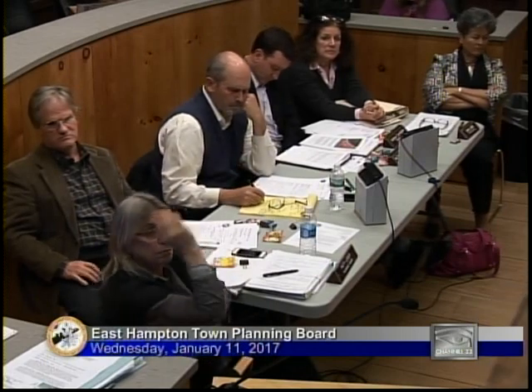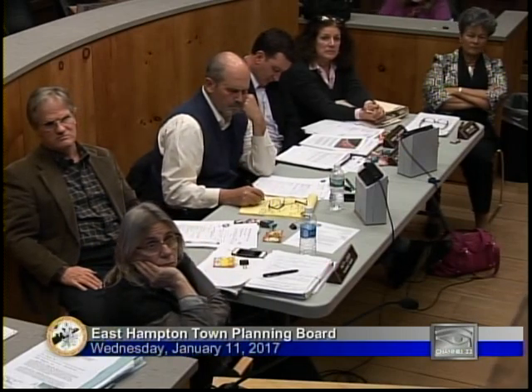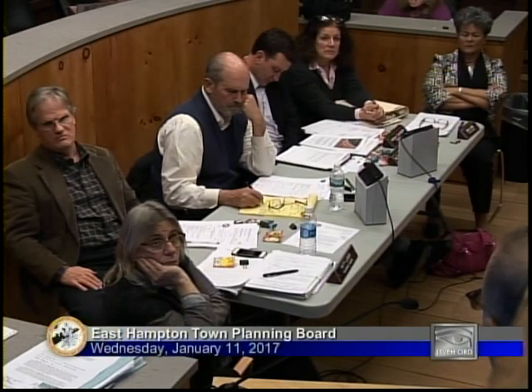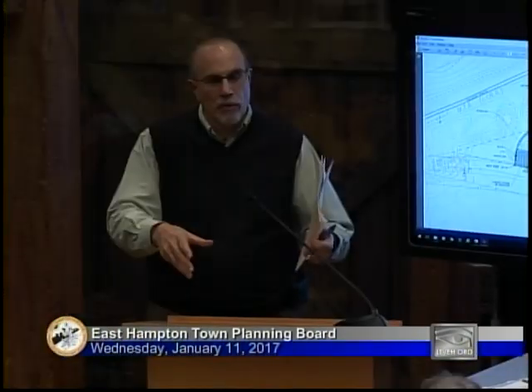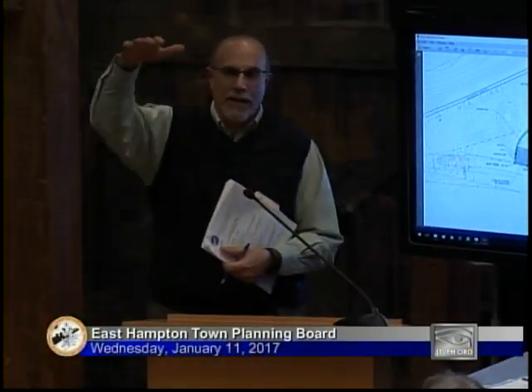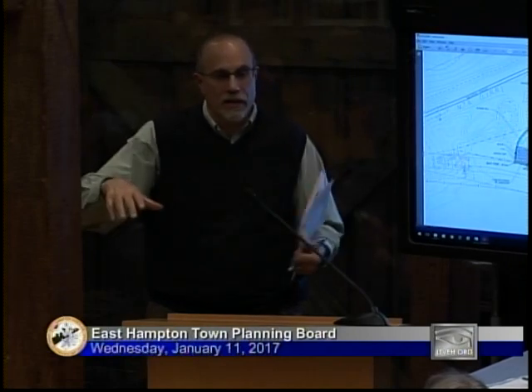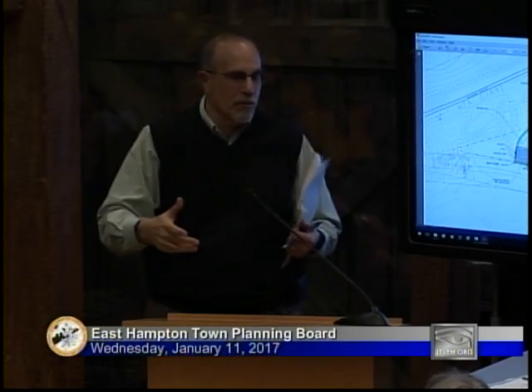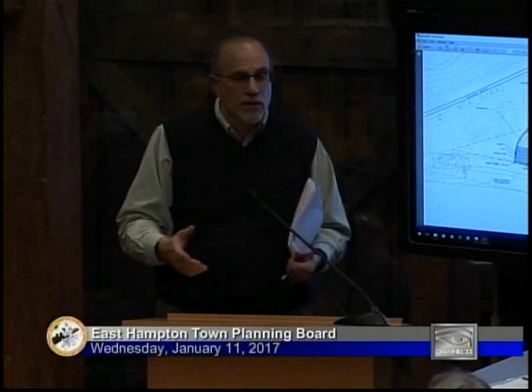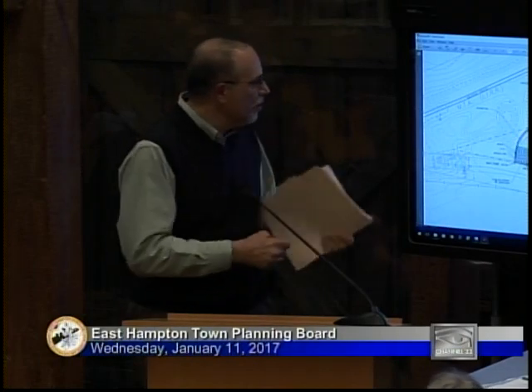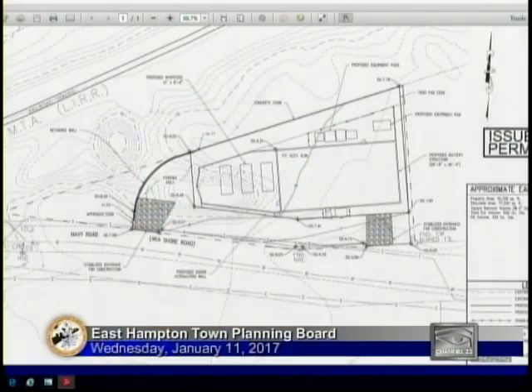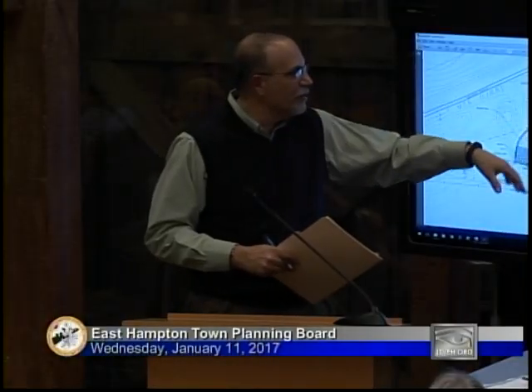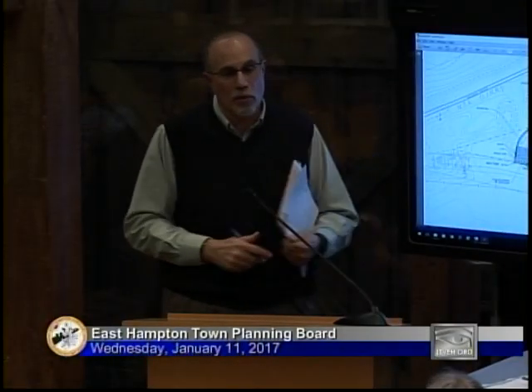When we do a noise model, we use a computer simulation, and we feed into it the manufacturer's noise readings for their piece of equipment. It takes the height the equipment's at, and all the different factors, mainly worst case. So when we look at the noise and do an isopleth against the property boundary, that's a worst case situation: all 4 HVAC units running, the 3 inverters on, and the transformer with all its fans on.